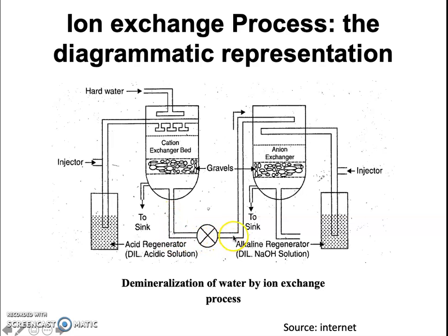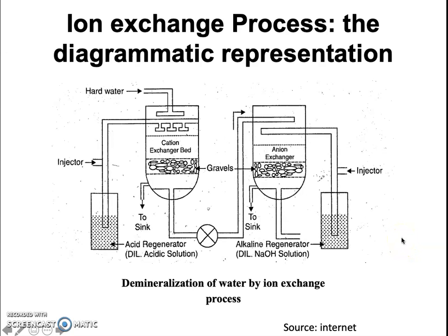When this water is allowed to pass through the anion exchange resin — a similar vessel containing gravels that support the anion exchange resin — all the anions get trapped into this bed. The water coming out as a result of the treatment process contains H⁺ ions and OH⁻ ions. Finally, the water ejected contains only H⁺ ions and OH⁻ ions, which combine to give demineralized water. This is the process of demineralization by the ion exchange process.